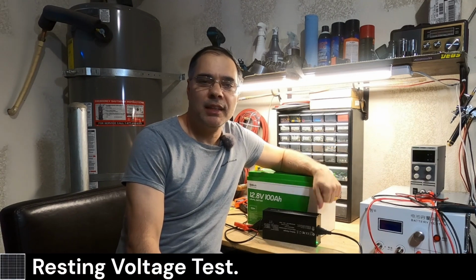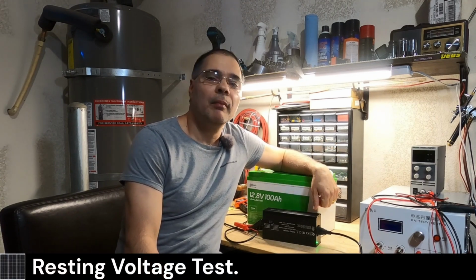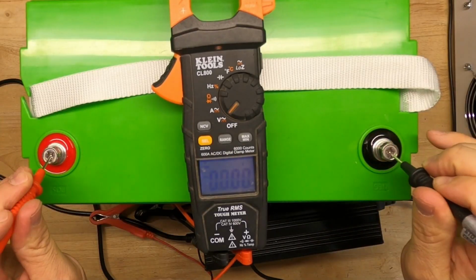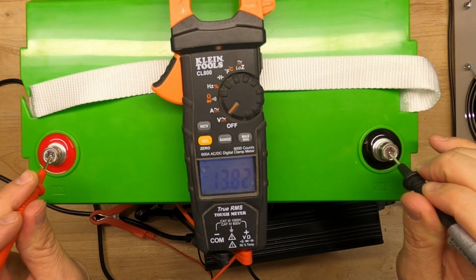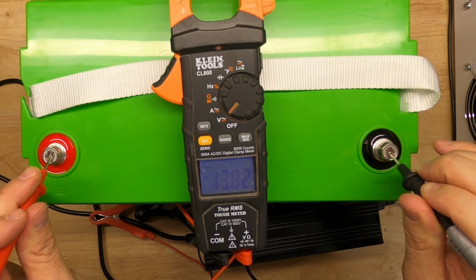On with the testing. Okay, so the battery's been fully charged and it's been sitting for about 12 hours. But before we do our capacity test, we're going to do a resting voltage test. The resting voltage is the voltage at which the battery settles down after the charge current has been removed. A good resting voltage is between 13.6 and 13.8 volts. So we're getting 13.82 volts, so that's pretty good.